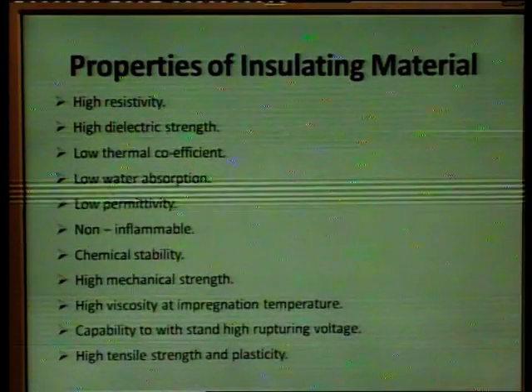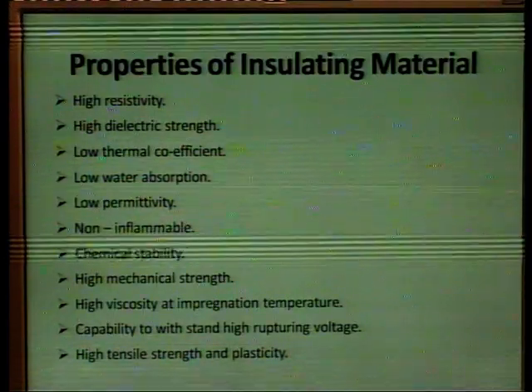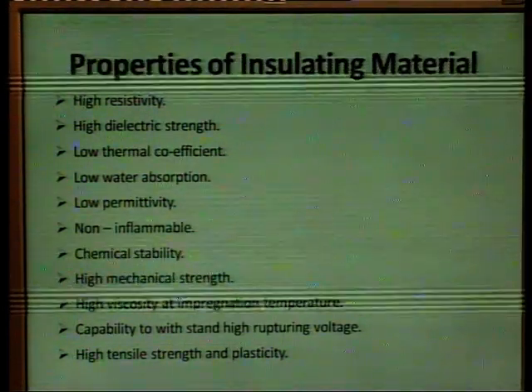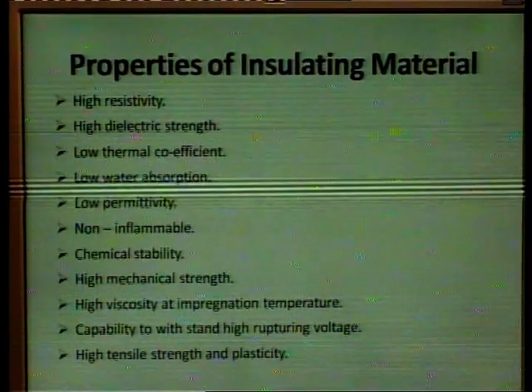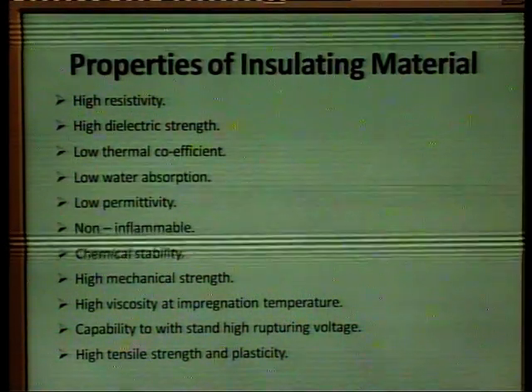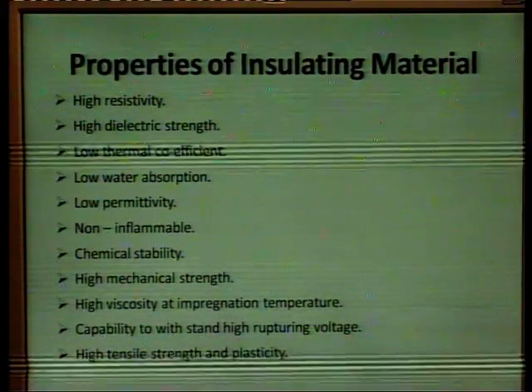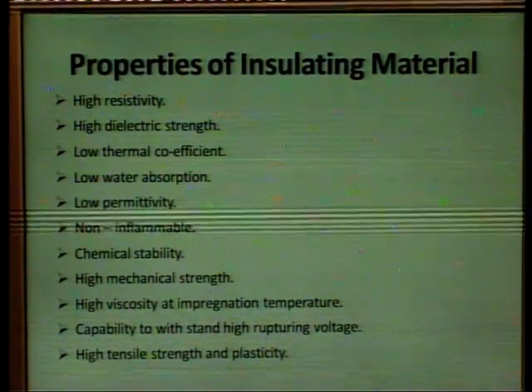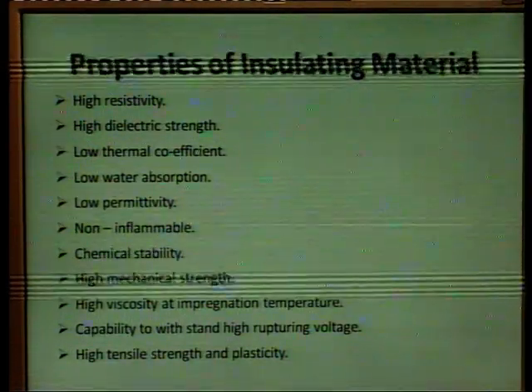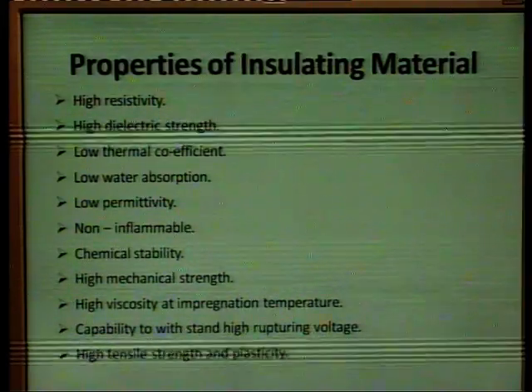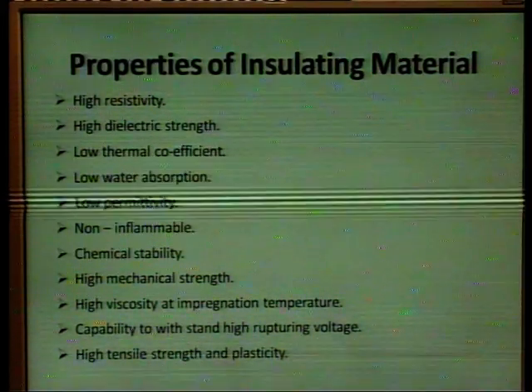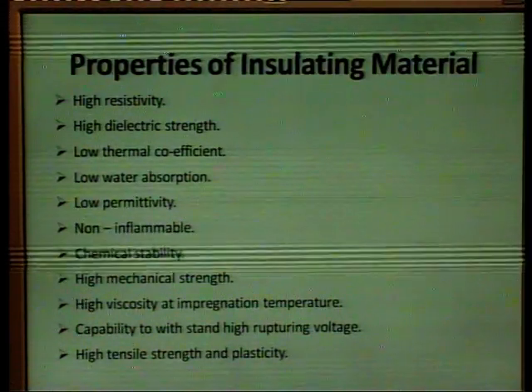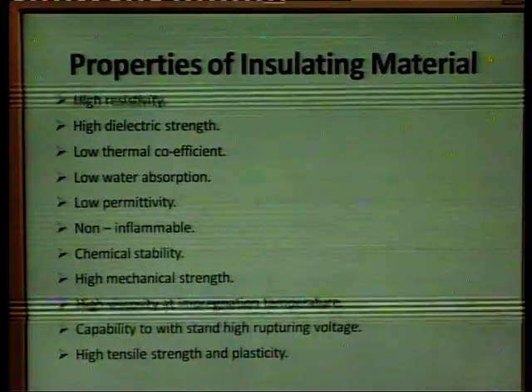Then the high mechanical strength should be there. The insulating material should have high mechanical strength so that it can withstand the various mechanical stresses when we handle the cables. Then the high viscosity at impregnation temperature, then the capability to withstand high rupturing voltages. It should have the capability to withstand the high rupturing voltages. Then it should have high tensile strength and plasticity. The tensile strength as well as the plasticity of the insulating material should be high.